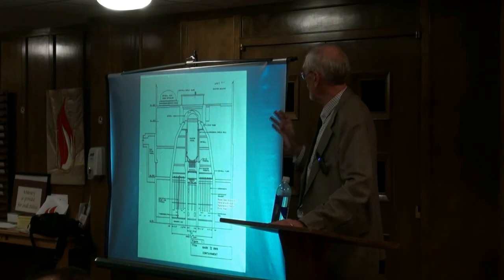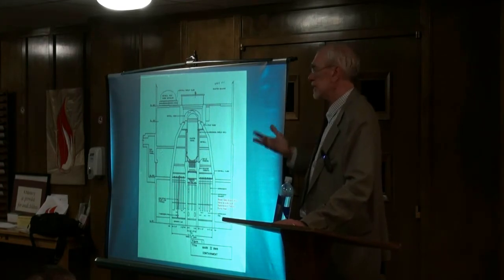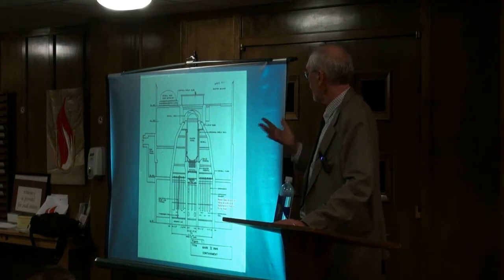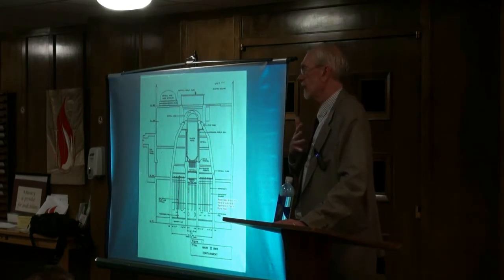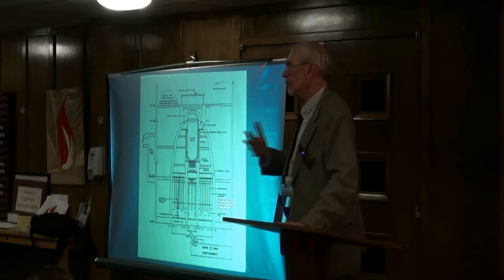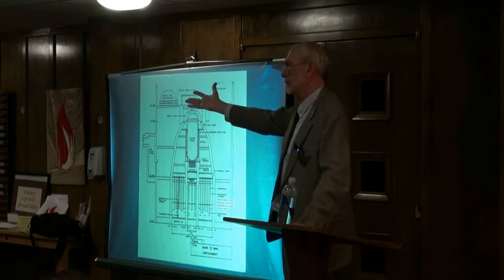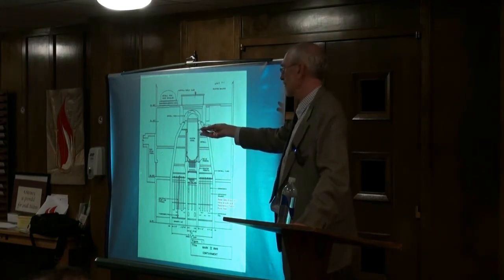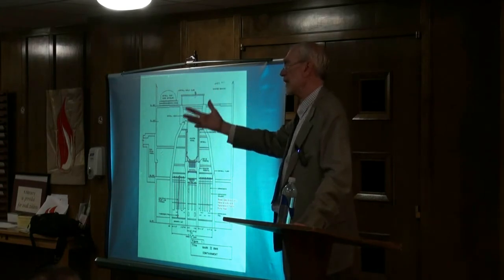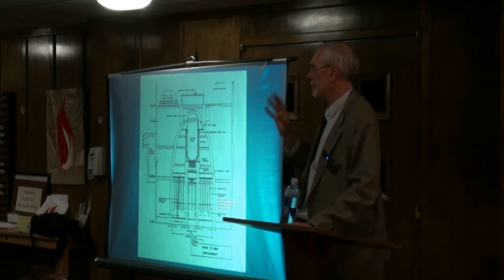Option 3 would put a high capacity filter in this vent line so that you would essentially capture all of the particulate, but you would capture none of the noble gas. You can't filter that stuff out. So that means radioactive krypton, radioactive xenon would escape as a gas, and then as a decay product, within a matter of seconds and minutes, it would rain out radioactive particulate of strontium-90 and cesium-137. So the decay chain in those noble gases is particulate. But it would filter out a good bit of it if they have this filter in.